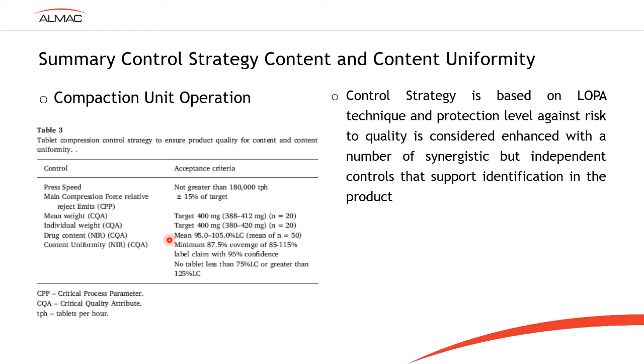So overall, as a reflection, this quality statement that we've given is valid for the entire batch, and as such, we've met the USP requirement that they state in that we must ensure that the batch is uniform, not just the tablets that we tested. If you compare how many tablets would normally be submitted at level 1 testing traditionally by HPLC, it is 10, so now we would test 50. Over time, we got better at doing it with the device, and we could probably go to 100, which would represent an order of magnitude increase. That number of tablets is sufficient to demonstrate the quality.